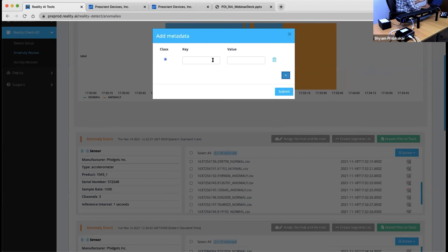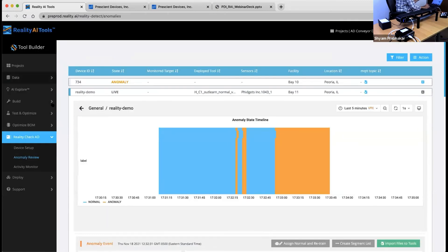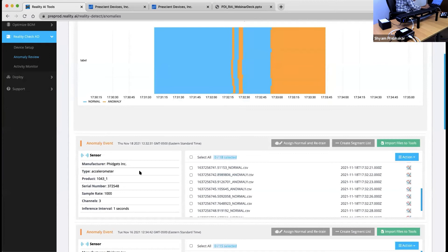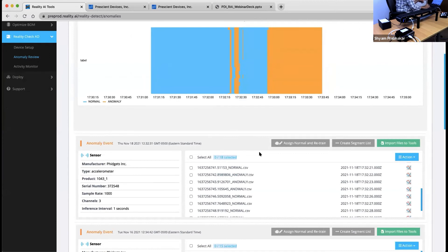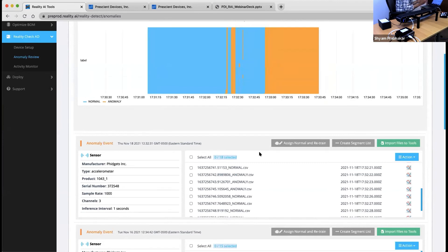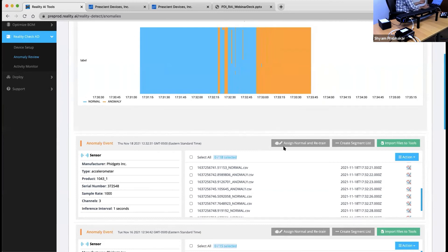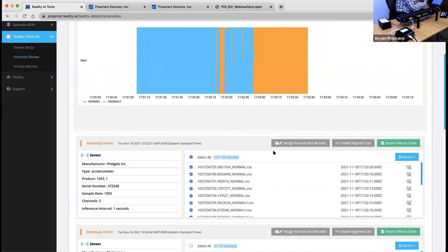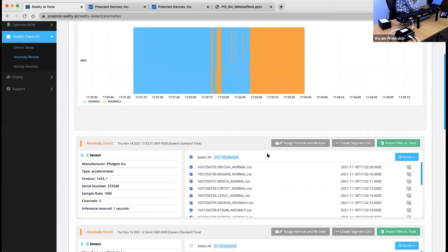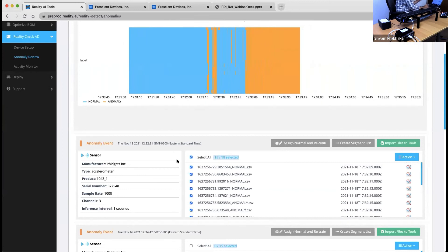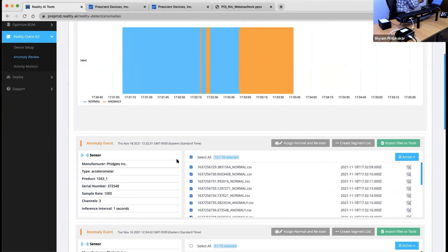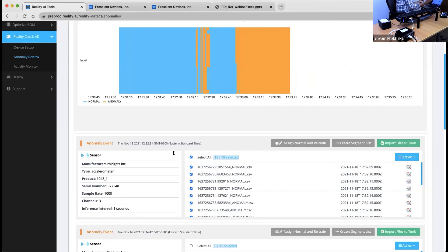You can actually look at the waveform and see how that looks. You can add some metadata to it. As Nalan mentioned, you could potentially use this down the road to build classifiers. Now that you have collected so much data, you can add a key-value pair to it, add some metadata, and then build a classifier using the flagship product. The last thing I want to show: if we were running the conveyor and it detected an anomaly that wasn't actually quite an anomaly — this is the human in the loop that Nalan mentioned — we can actually go ahead and assign normal and retrain for that specific anomaly that we just saw. We're telling the anomaly detection model: that anomaly you just saw is actually not quite an anomaly, so add it to your baseline, and in the future we won't mark that as an anomaly.